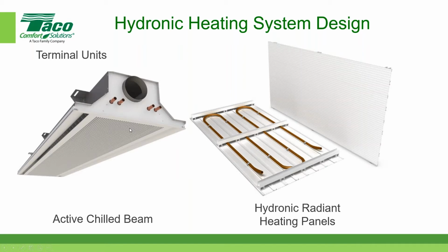An active chill beam, and you can see the connections here. This happens to be what is known as a 4-pipe active chill beam, where we have both hot water and chilled water connections. But since we're talking about heating systems, we'll just think of this pipe here going in. Maybe that's going in on that side, and the return water is coming out on this side here. So that's where our piping system would be connected to an active chill beam. That's what we got down here.